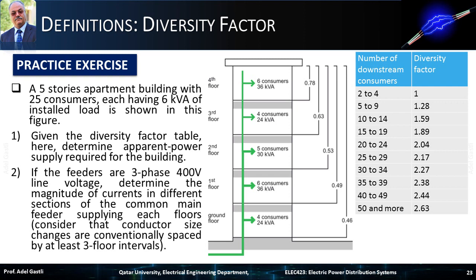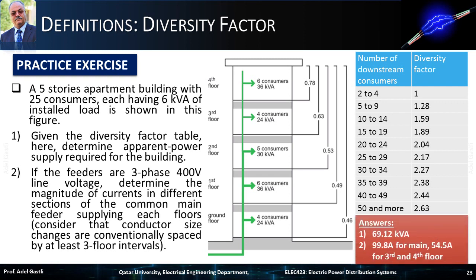The final answers are 69.12 kVA for the apparent power supply required for the building, 99.8 amps for the main feeder going up to the second floor, and 54.5 amps for the feeder supplying the third and fourth floors.